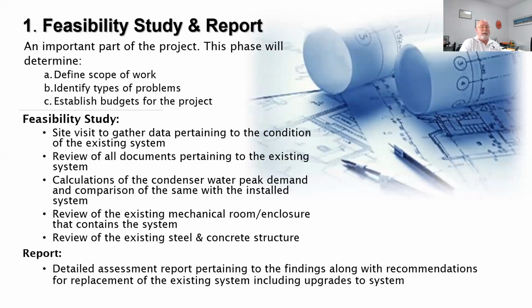But sometimes the tag is so badly worn, or the tower is so old, that I have to start doing other things, like measuring pipe sizes and looking for other clues as to tower sizing. Then, at that same time, I review the existing steel and concrete structure.